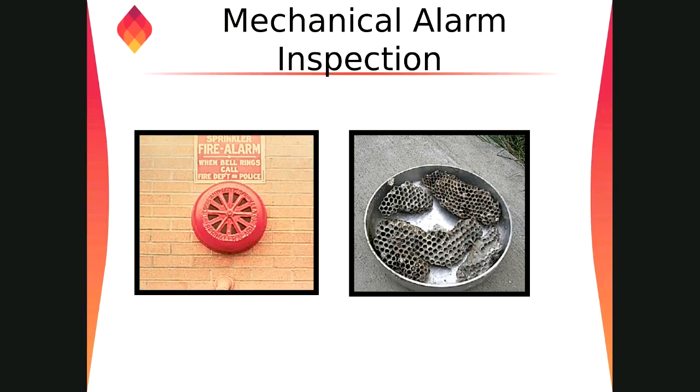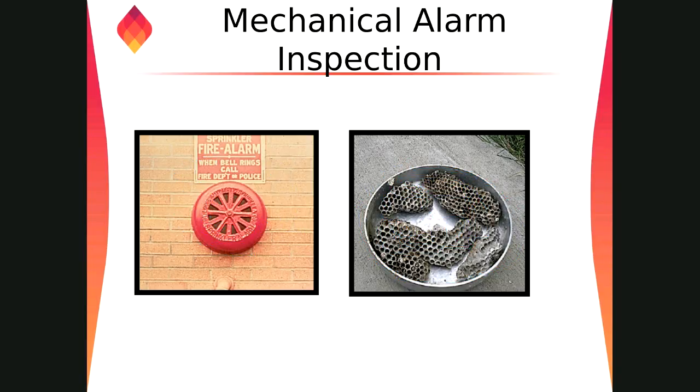And when the inspector goes to the site and looks, there is a honeybee nest, right? So when there is a fire and water is coming, it tries to rotate the blade on this steel. There will be no sound, or the sound will be totally different and much less compared to the design one. So it is not acceptable.